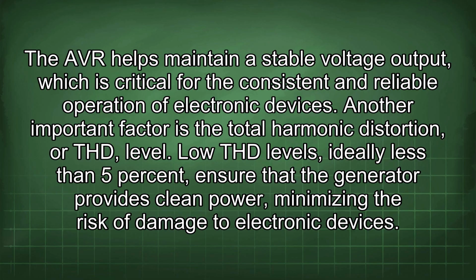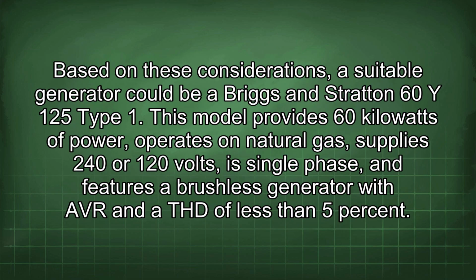Another important factor is the total harmonic distortion, or THD, level. Low THD levels, ideally less than 5%, ensure that the generator provides clean power, minimizing the risk of damage to electronic devices. Based on these considerations, a suitable generator could be a Briggs & Stratton 60Y125 Type 1. This model provides 60 kilowatts of power, operates on natural gas, supplies 240 or 120 volts, is single phase, and features a brushless generator with AVR and a THD of less than 5%.